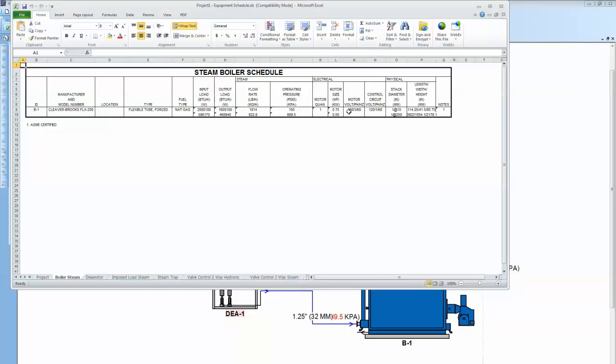These are schedules that go on your drawings because you have the schematic that goes on the drawings, shows the contractor the sizes and how things need to be piped up. The schedules have capacities and information. And then the other thing we put on our drawings obviously would be our AutoCAD or Revit drawings that shows how things fit in the space. So when we put a drawing out in our consultant firm, those are the three things that our drawings are comprised of obviously the specs too.